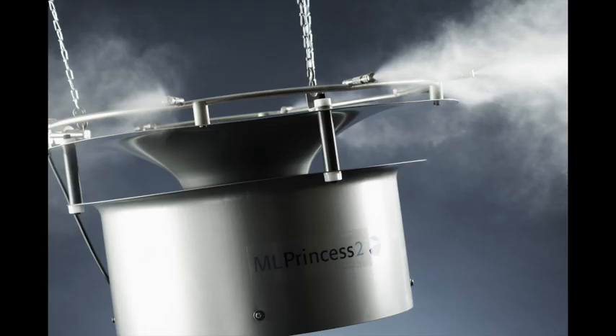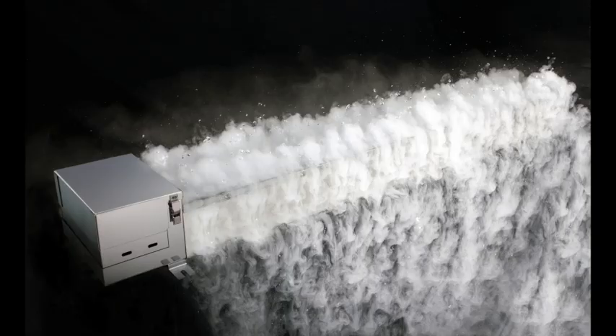Next, there are spray humidifiers. These are ideal for large areas when humidifying directly into a room. They can give up to 750 kilos per hour from a single system, but can also be used inside an AHU with lower outputs. And they do offer an added benefit of cooling alongside humidification. In fact, any cold water humidifier will do this for you. Another type are ultrasonic humidifiers, and these tend to have smaller outputs, so are useful for small areas like a humidor or a display cabinet.